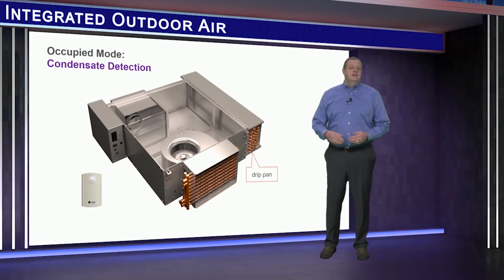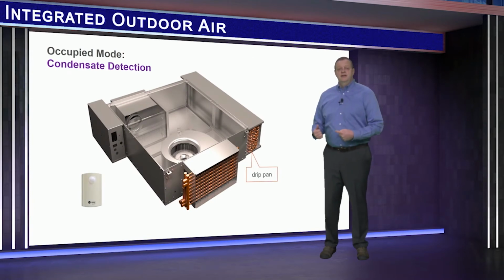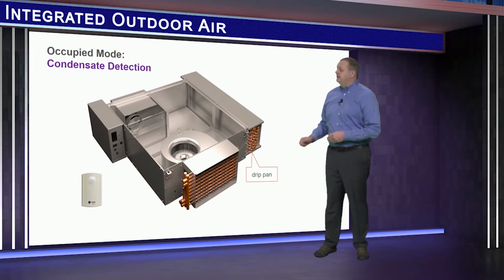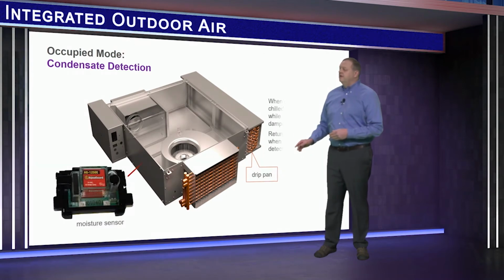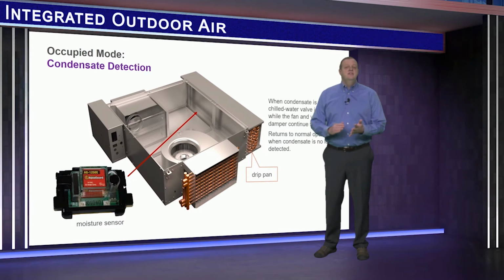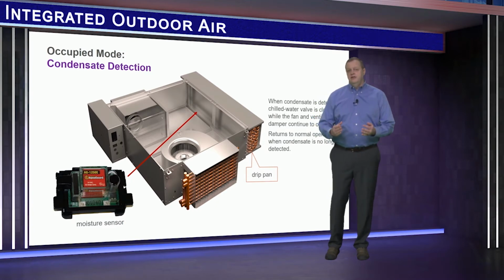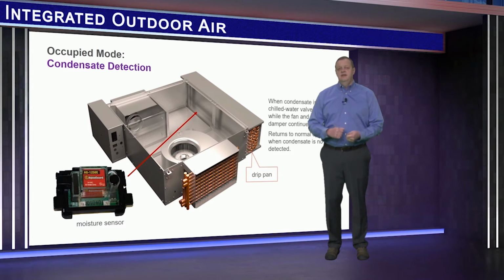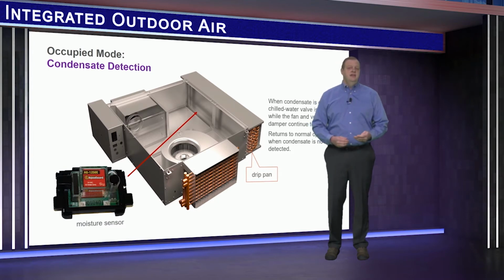In addition, like I mentioned earlier, all Trane terminals are built with a drip pan located underneath this sensible cooling coil. If the moisture sensor in this drip pan ever detects the presence of condensate, the controller temporarily closes the chill water valve and continues operating the fan and ventilation air damper as normal. Once condensate is no longer detected, the valve is allowed to open again.